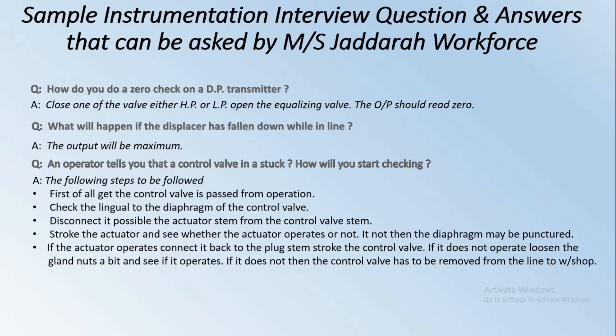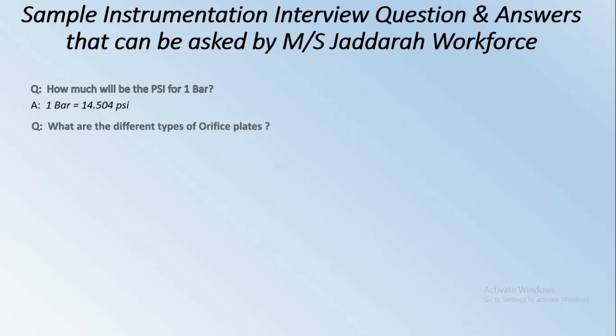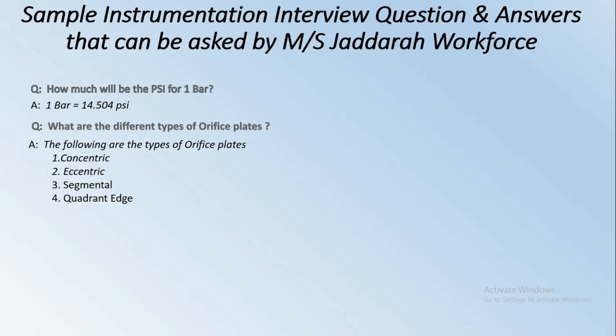If the control valve does not operate, loosen the gland nuts a bit and see if it operates. If it still does not, the control valve has to be removed from the line and sent to the workshop. Next: How much is one bar in PSI? One bar equals 14.504 PSI. The types of orifice plates are: concentric, eccentric, segmental, and quadrant edge.